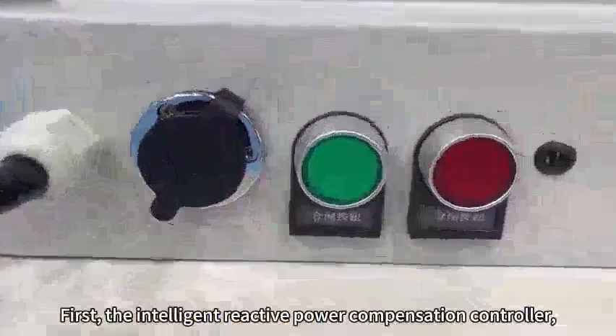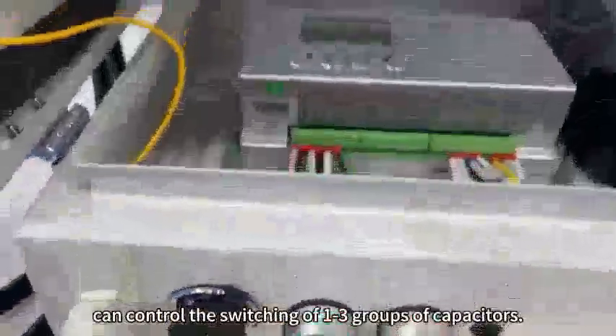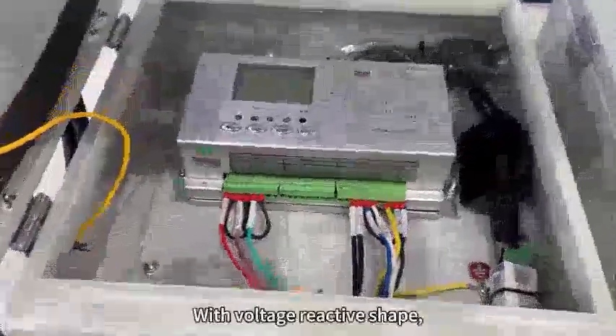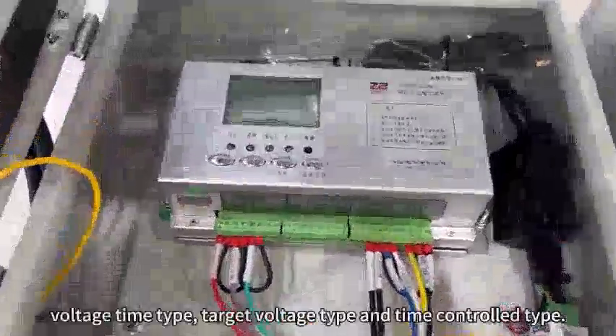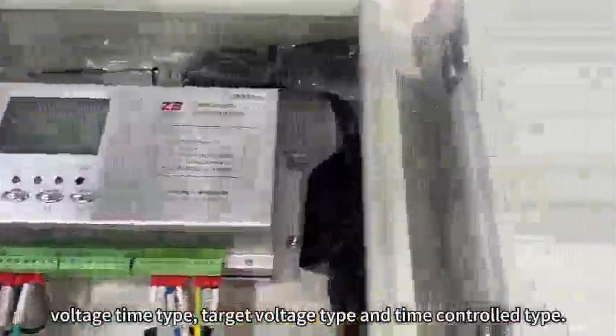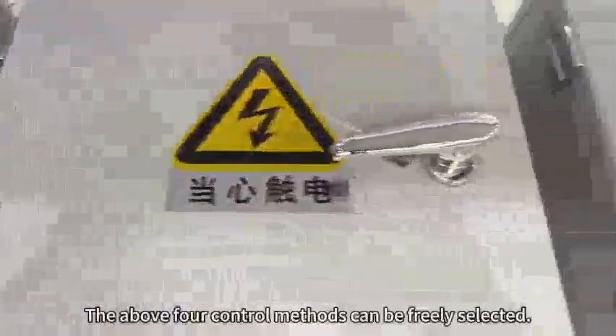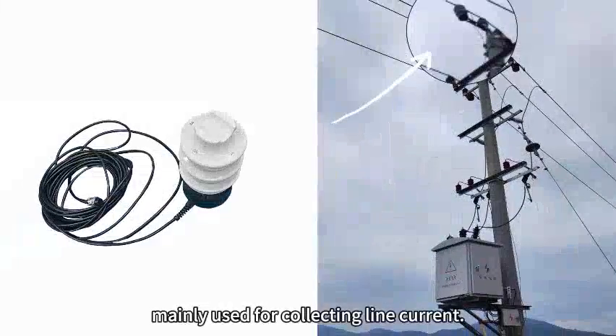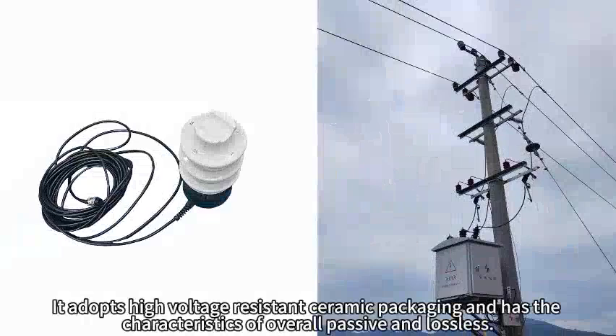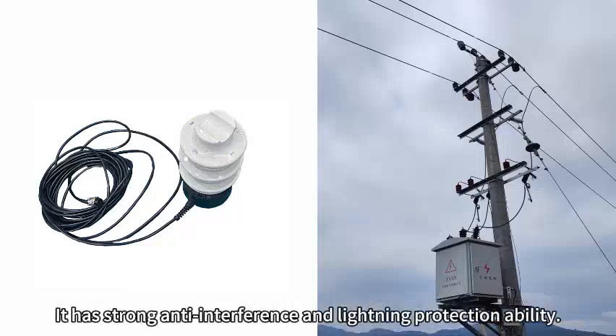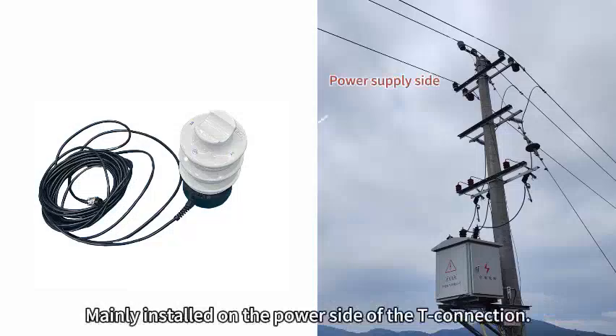First, the intelligent reactive power compensation controller can control the switching of 1 to 3 groups of capacitors with voltage reactive type, voltage time type, target voltage type, and time control type. The above 4 control methods can be freely selected. The current sampling sensor is mainly used for collecting line current. It adopts high voltage resistant ceramic packaging and has the characteristics of being overall passive and lossless. It has strong anti-interference and lightning protection ability, and is mainly installed on the power side of the T connection.